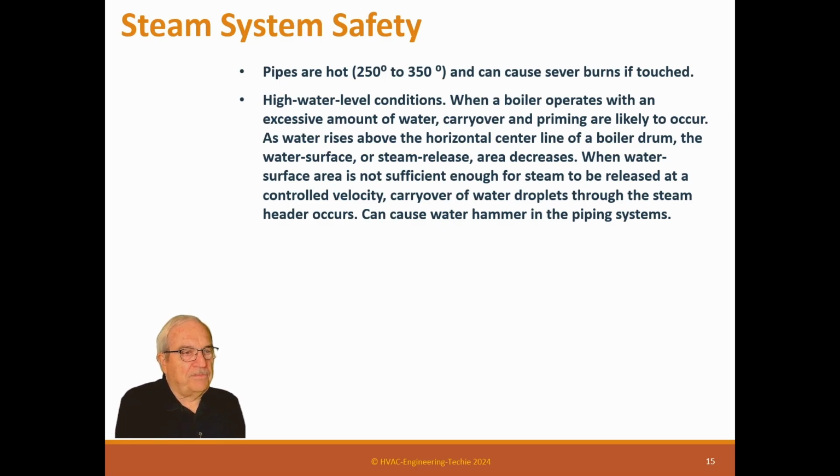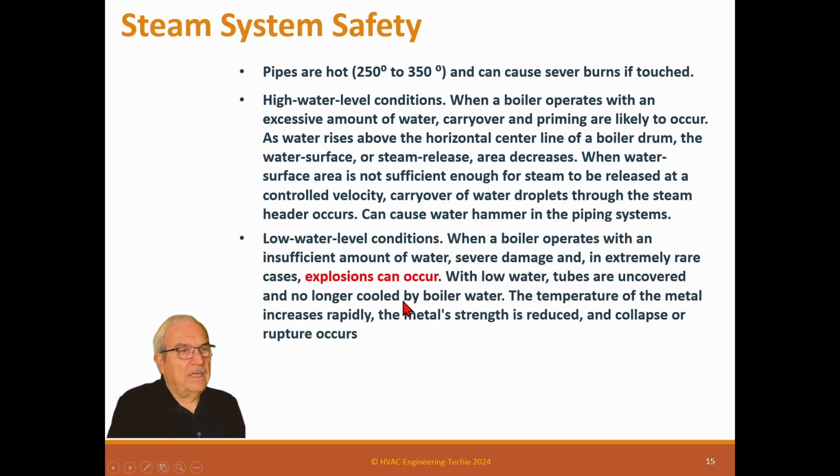So remember, the piping system on a steam system doesn't like two things. They don't like air, and they don't like water. Now, they got condensate in there, but they're trying to push that in, but they don't want a pipe full of water. You know, if you have a pipe designed incorrectly for the steam load and has too much condensate in it, as the steam pushes it down the pipe, it can become a solid block of water. And when it becomes a solid block of water, it can cause water hammer. The reason is, remember, steam is moving at 20,000 feet per minute or so. It's moving really, really fast, and water's moving really, really slow. So what happens here when you have too much water in a boiler, it basically fills the pipe up with water, and it can cause water hammer, which can burst the pipe, and then can cause live steam into the space. So this is important, but this one's more important.